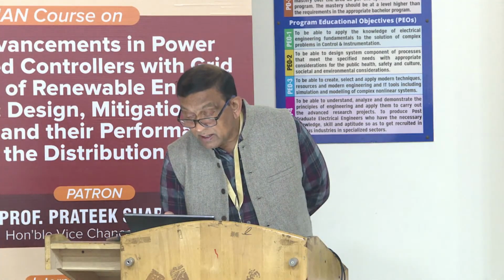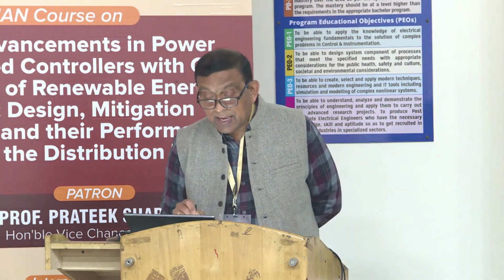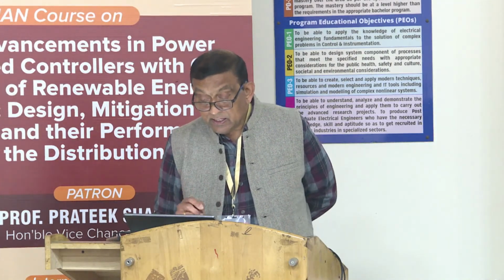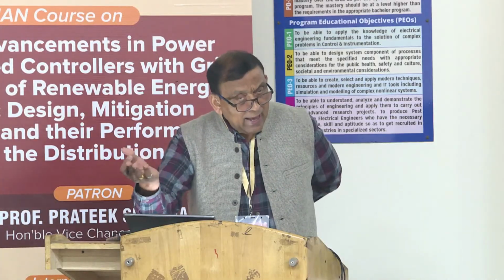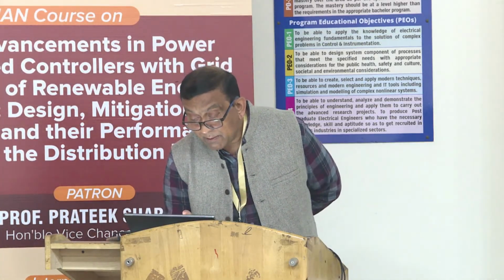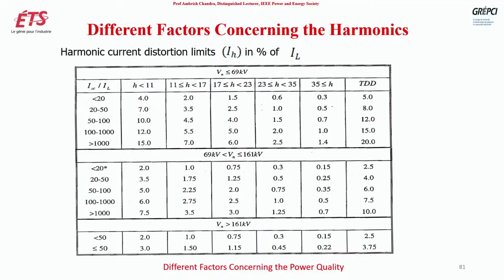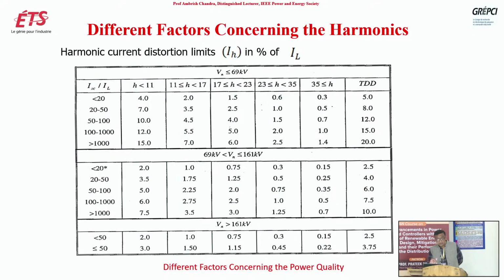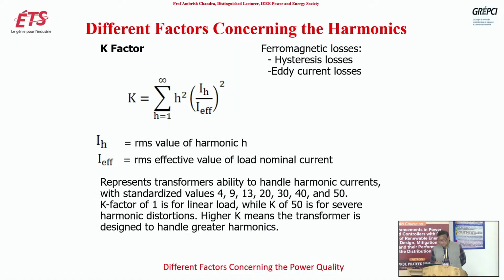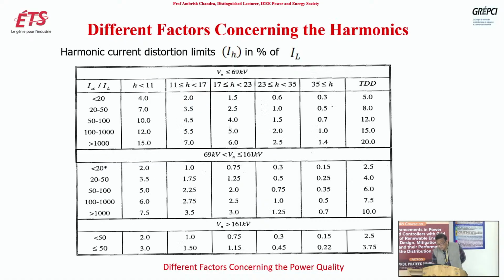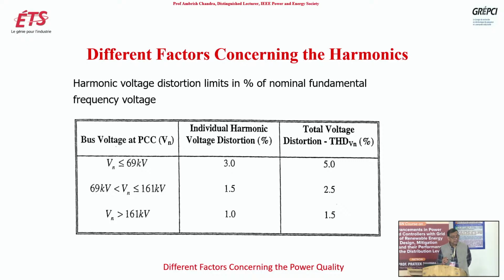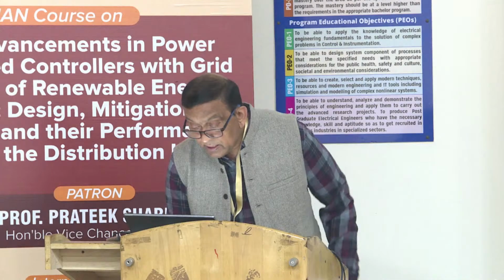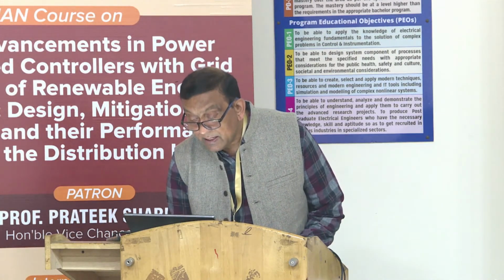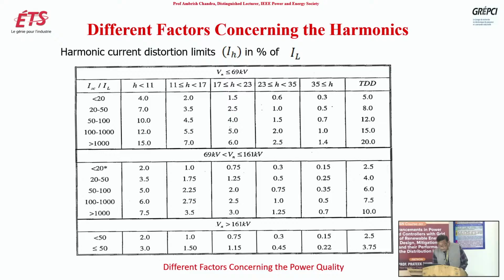So this is how you can interpret it: as the distribution system size increases, you can tolerate a higher level of harmonics. But as the harmonic ranking is increasing, you have to have more severe limitations on the harmonic limit, as well as on the THD. This was for voltage less than or equal to 69 kV. But if voltage level is between 69 kV and 161 kV, then you see it is half of these.